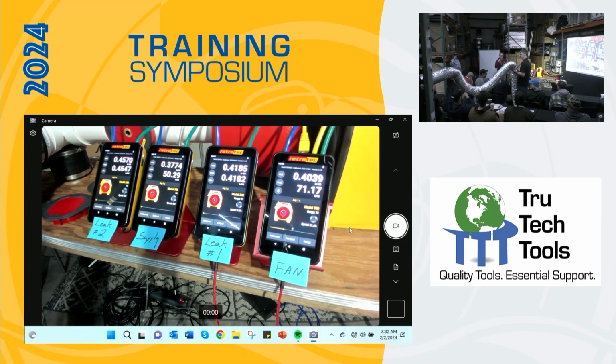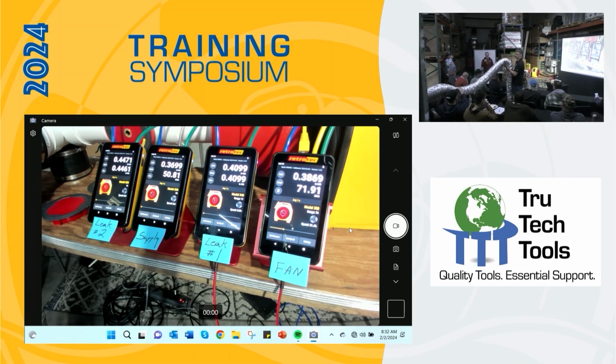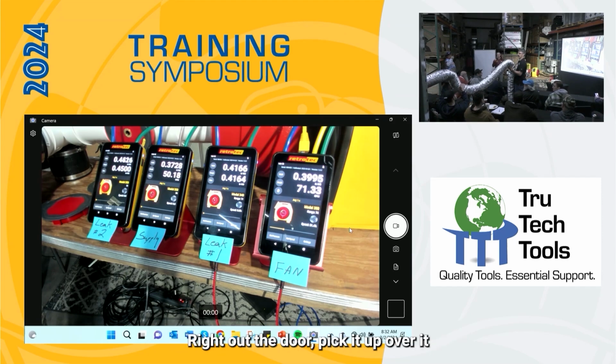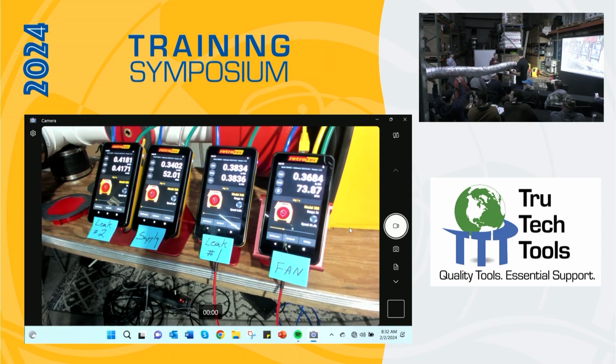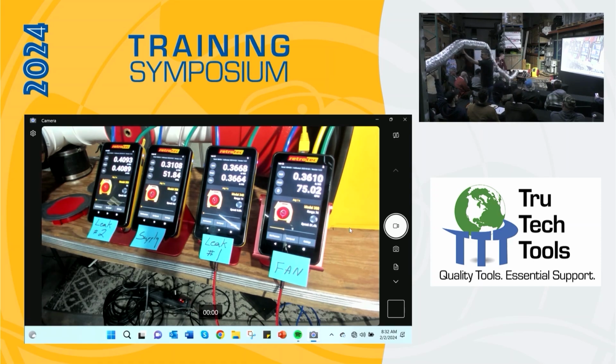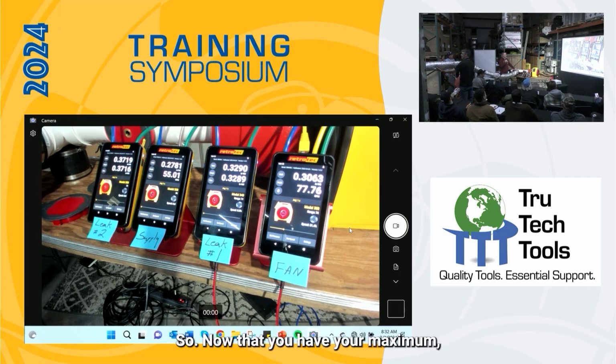Sure. This is just one duct. There would be a lot more. And usually installers are consistent, so if one's going to be bad, a lot of them are going to be bad. Yeah, we're getting more flow, and the pressure's dropping a little bit.